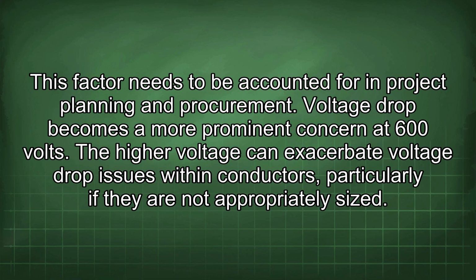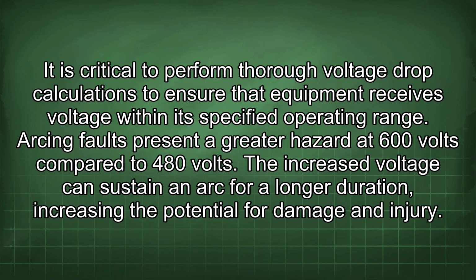Voltage drop becomes a more prominent concern at 600 volts. The higher voltage can exacerbate voltage drop issues within conductors, particularly if they are not appropriately sized. It is critical to perform thorough voltage drop calculations to ensure that equipment receives voltage within its specified operating range.